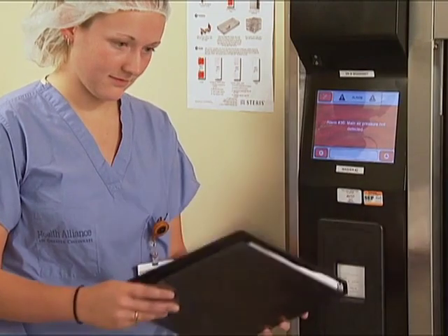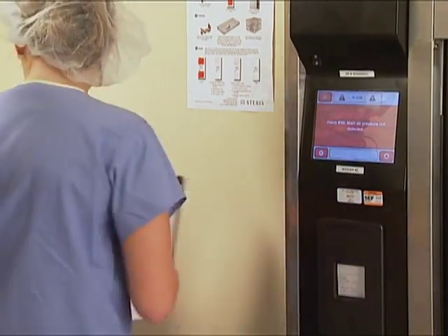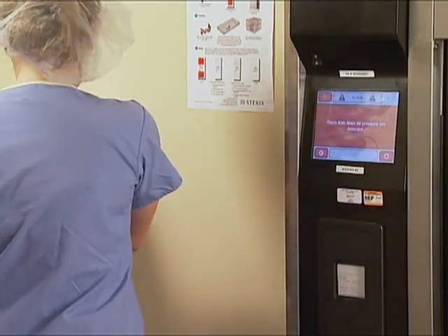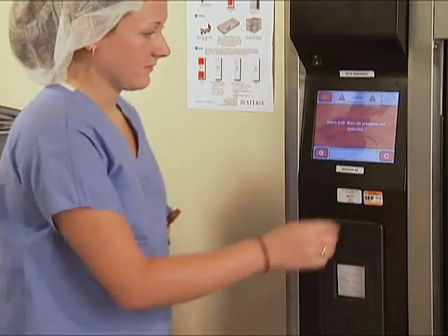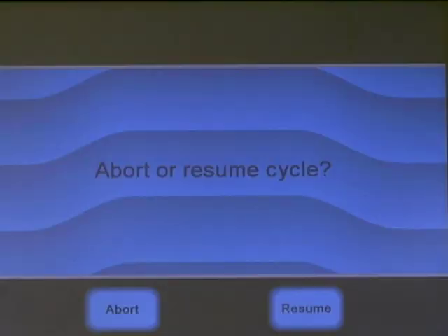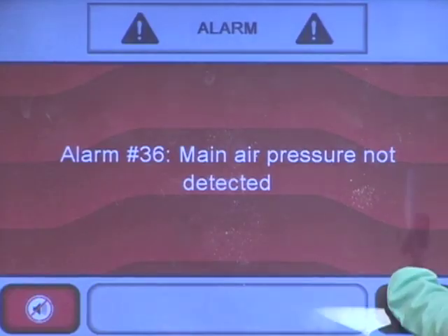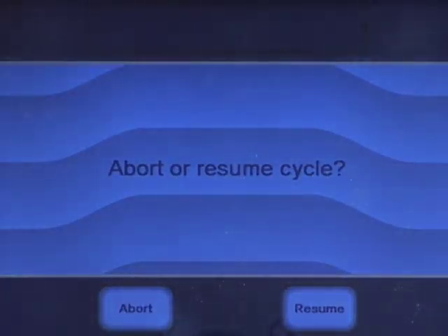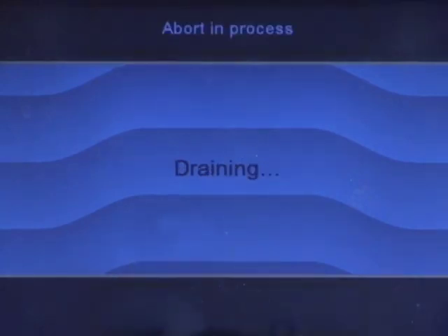Again, refer to the Alarms Messages chart in Section 7 of the Vision single-chamber washer operator manual for how to fix the issue. Once you have resolved the alarm, press Resume to continue processing the load. The cycle returns to the beginning of the interrupted phase. If the alarm requires you to abort the cycle, press Abort. The water is automatically drained and the PC control screen returns to Ready mode.